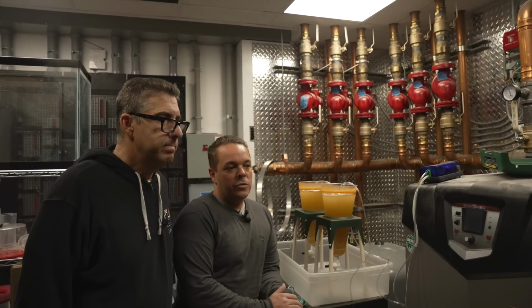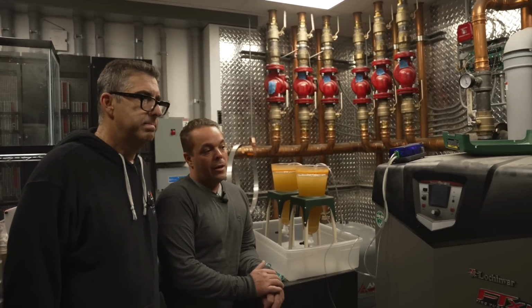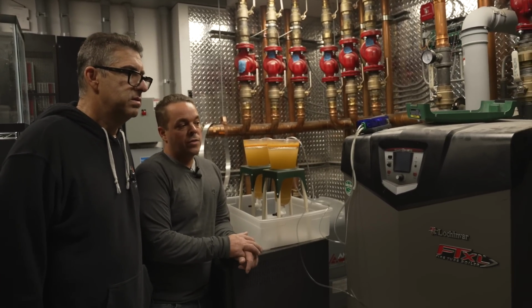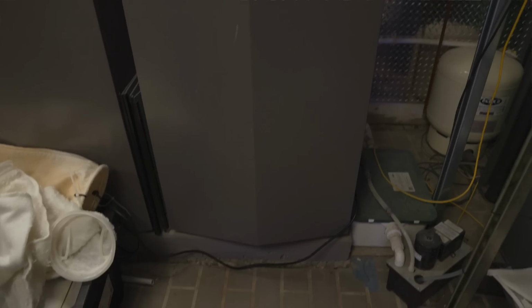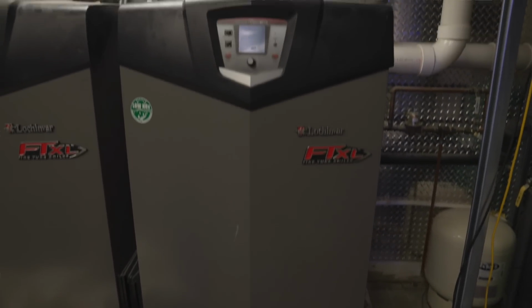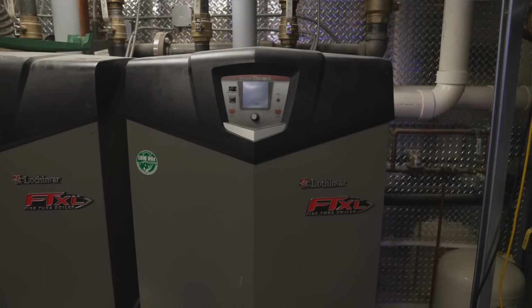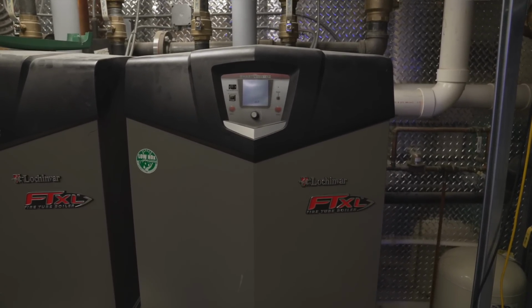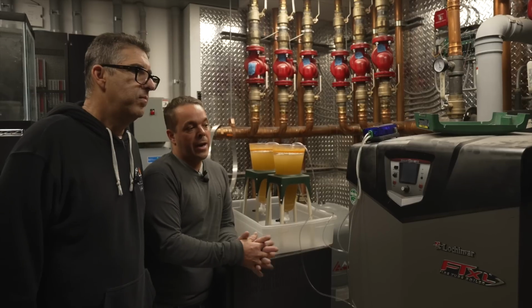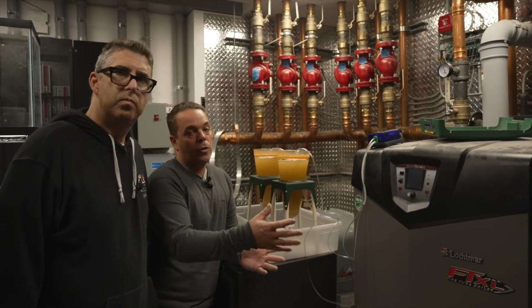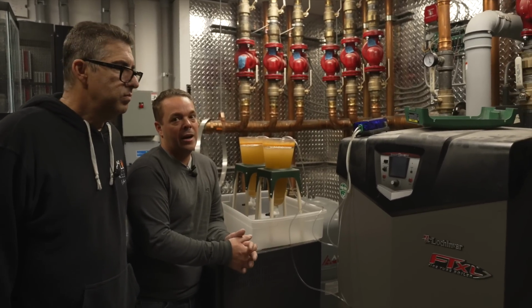This is our heating source for the aquarium and all the water change tanks as well. These are 2 600,000 BTU boilers, each one being 600,000 BTUs. Depending on how cold the water is coming back, either one will turn on or they'll both run simultaneously if we need a higher heating demand.